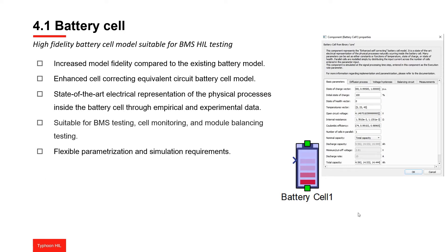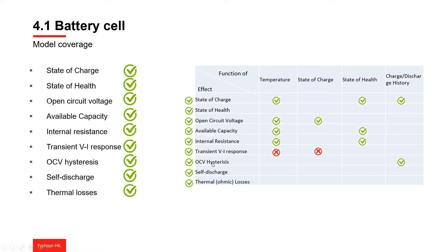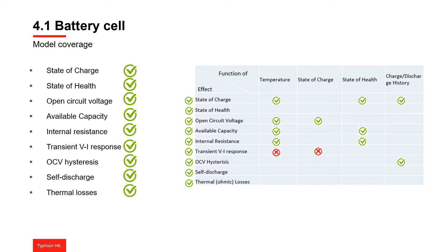The battery cell component supports testing of state of health and temperature dependent parameters such as capacity, internal resistance, and Coulombic efficiency, among others. Open circuit voltage can now also be dependent on temperature in addition to state of charge. Open circuit voltage hysteresis effects and transient dynamics due to slow diffusion processes are also included. The new battery cell component also enables various fault condition tests, self discharge emulation, and the inclusion of balancing circuits.